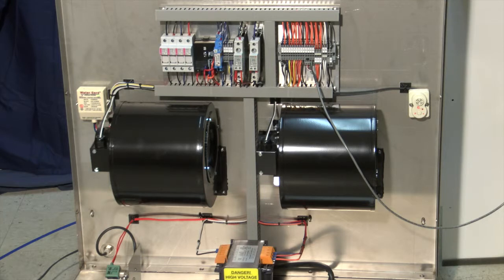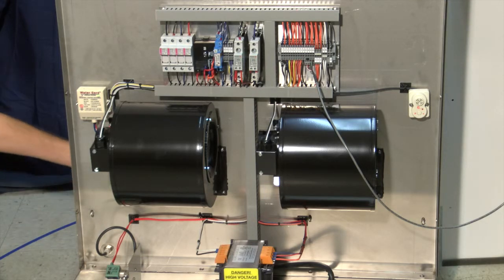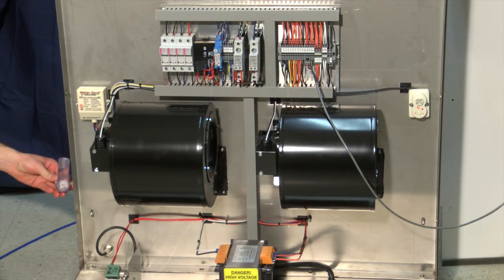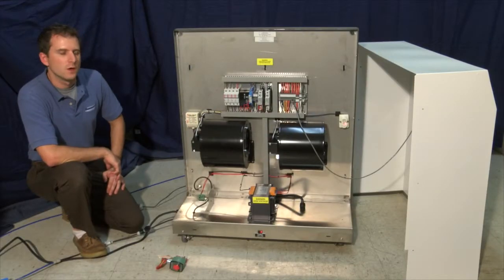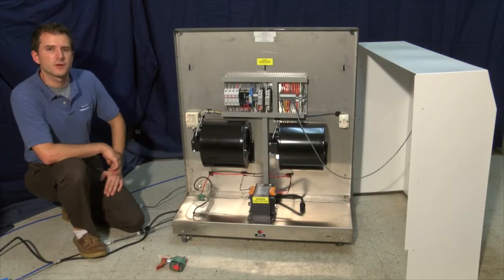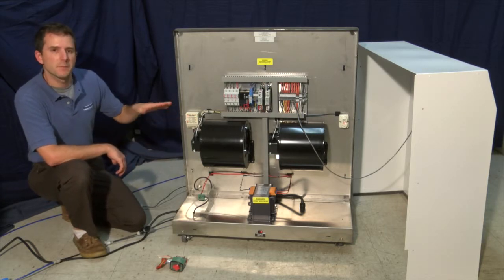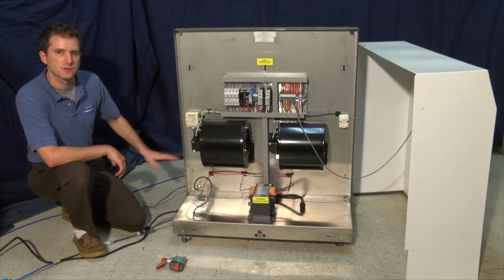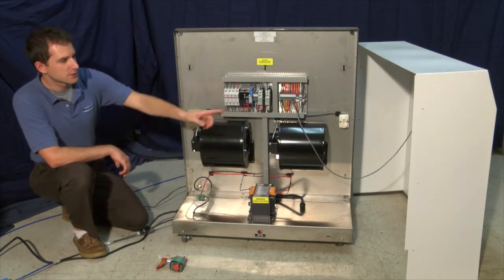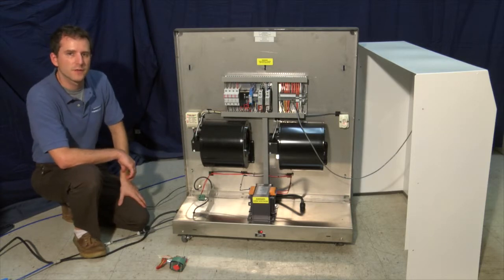In the event of an overflow, the sensor tube would fill with water, and there is a delay on the sensor tube in order to prevent false alarms. Once water has been in contact with the sensor tube for the proper amount of time, the water guard control will be triggered. When the water guard system is triggered, the following things occur. First, the water guard will shut down power to the unit, deactivating the fans and transducers to protect the humidifier system. It will also send out the loud audible alarm, letting you know that there is a problem.